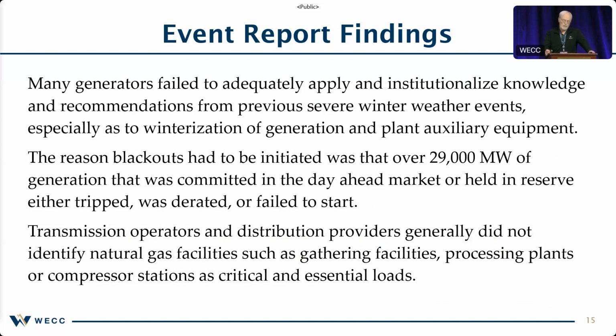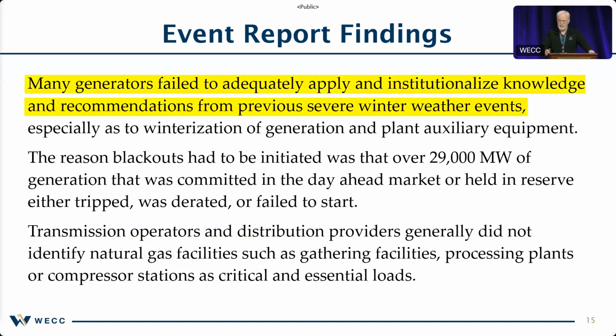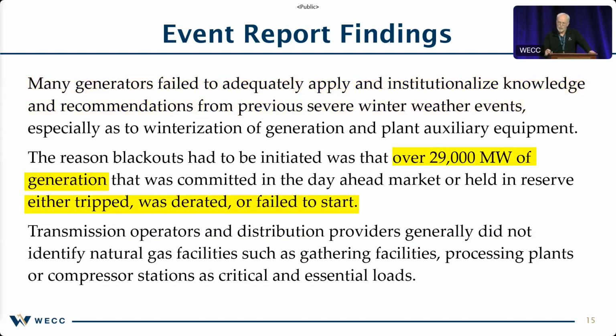When they looked at the event report, they did their investigation, and there's a ton of information on the 2011 event out there. But what they recognized was many of the generators failed to adequately apply and institutionalize knowledge and recommendations from previous severe weather events. So they didn't look at lessons from the past and apply them to their system. Over 29,000 megawatts of generation that was committed in the day-ahead market either tripped, derated, or failed to start. So when they were forecasting the generation that was going to be forced out of service, they didn't forecast enough. They lost more generation than they anticipated to. And that led to that load generation imbalance.